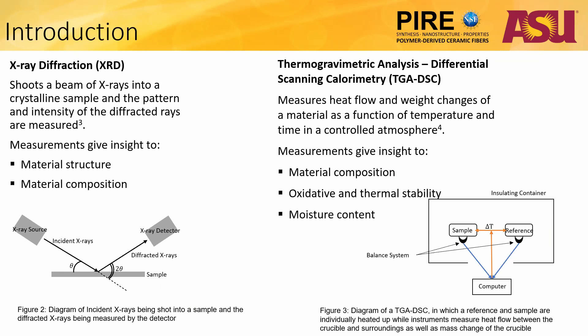XRD is a process in which a beam of x-rays are shot into a crystalline sample, and their diffraction pattern and intensity are measured. These measurements give insight to the structure and composition of a material. An X-ray source emits incident X-rays at an angle of theta, and the rays are diffracted by the sample and measured by an X-ray detector again at an angle of theta. The intensity of these rays are measured and plotted against 2-theta because the angle must be with respect to the incident rays rather than the sample.